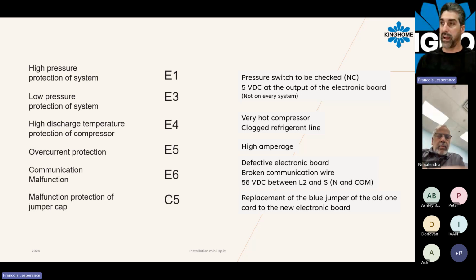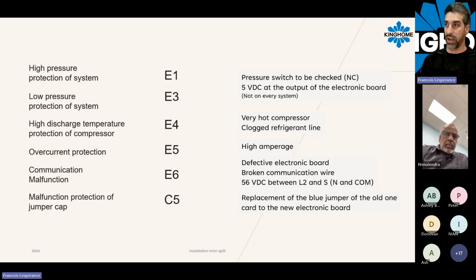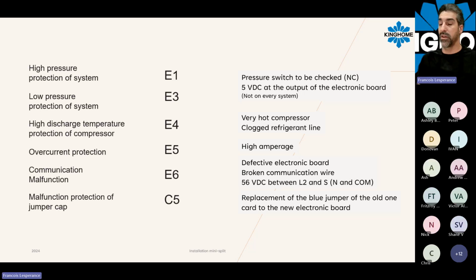Maybe you will not find a pressure switch each time. It's not on every system. It really depends on the total amount of refrigerant on the system before they decide to add a pressure switch or not. But most systems have one, so it's always a good thing to know, when you get an E3 error, for example, to make sure your switch is normally closed, or if it's open, that it's because it is open on a low pressure. But if it's closed, make sure you have 5 volts DC on the output on the electronic board.